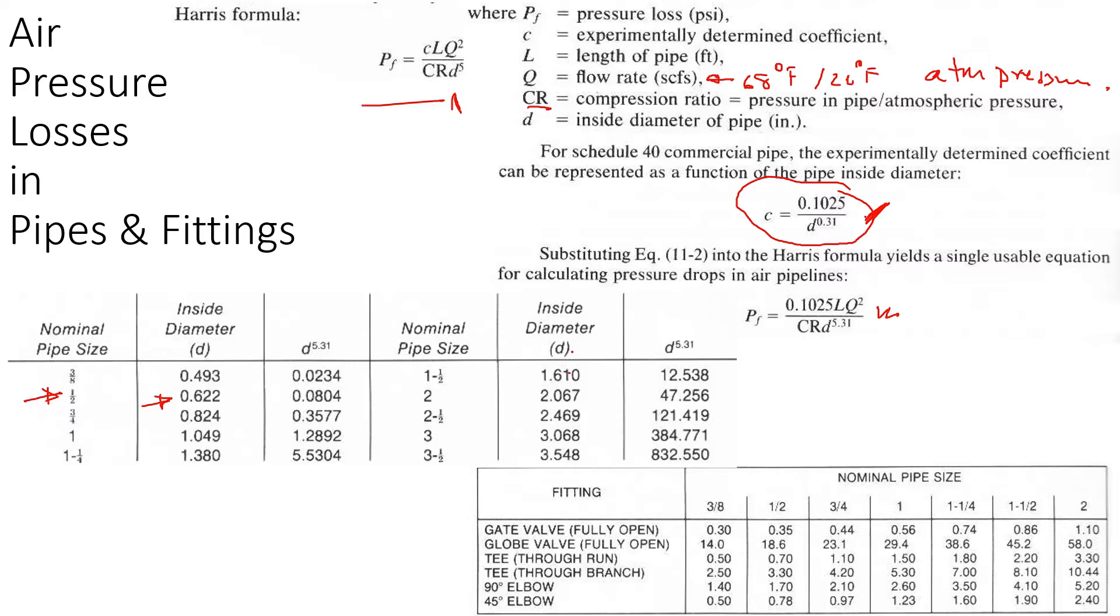To calculate length we have to also consider fittings like Ts, 90 degree elbows, 45s. In hydraulics we separately calculate the losses, but here you can simply use this available table for the equivalent length.